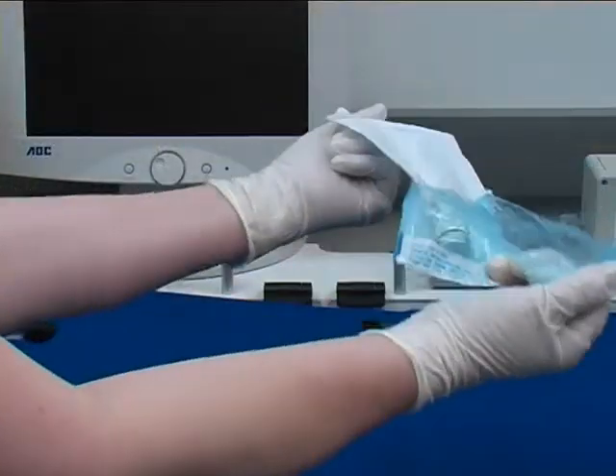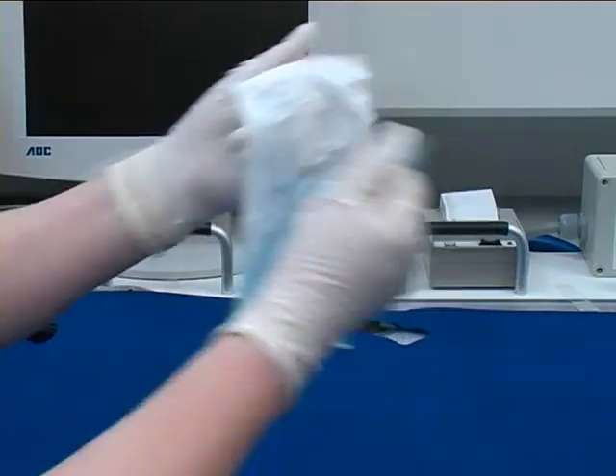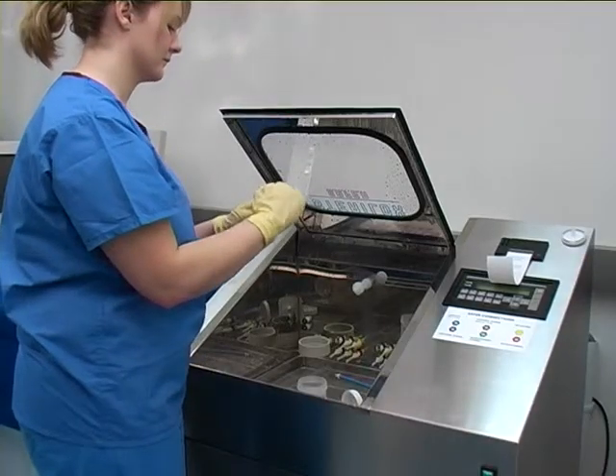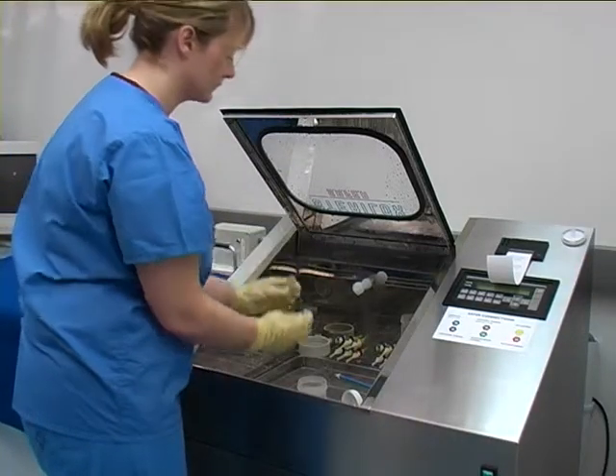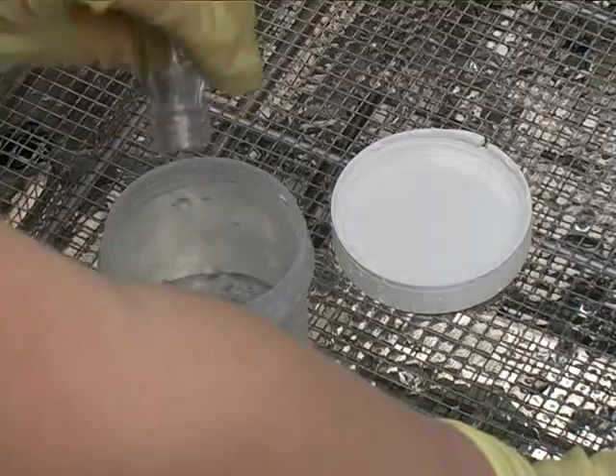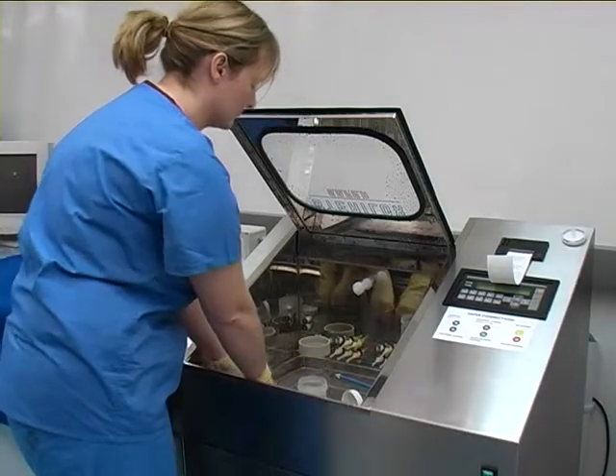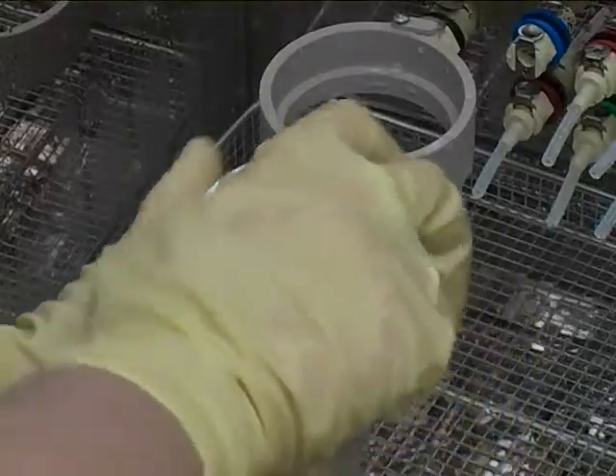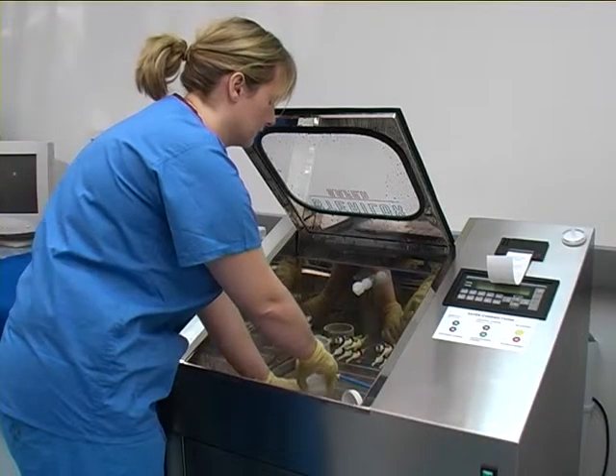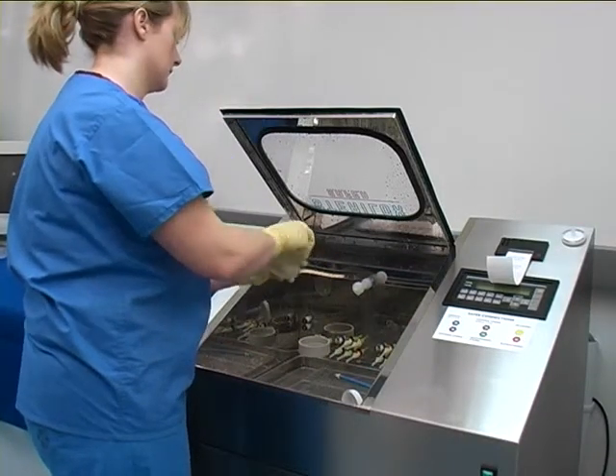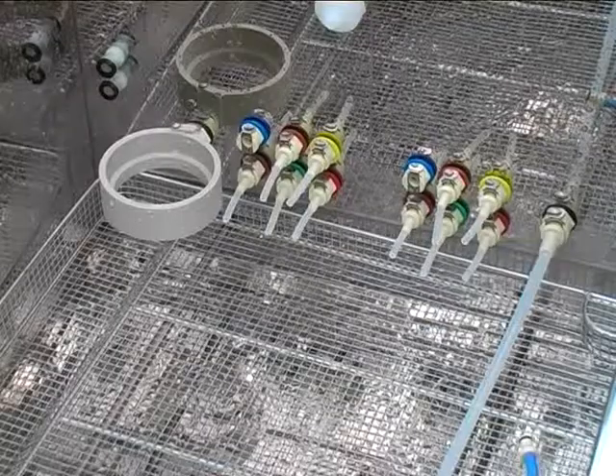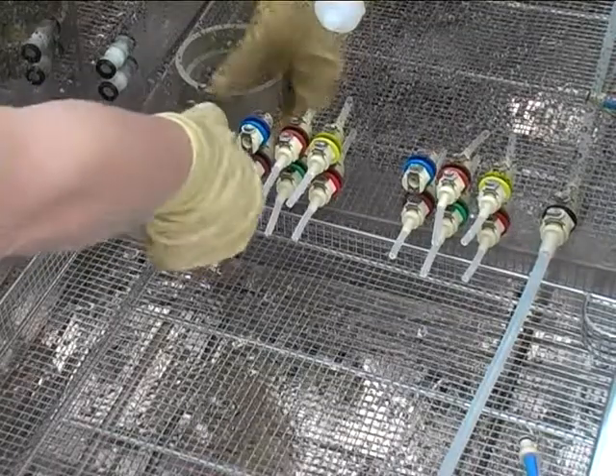An assistant must help you to open ampule pouch in order to maintain asepsis. Add the ampule of sodium thiosulfate. To make the bottle watertight, seal with cap from chamber. Strict aseptic conditions should be maintained when replacing cap. Finally, you should remove the ring holder from leak tester port and dry.